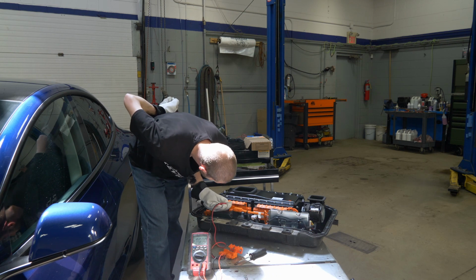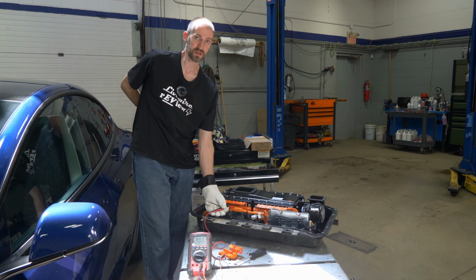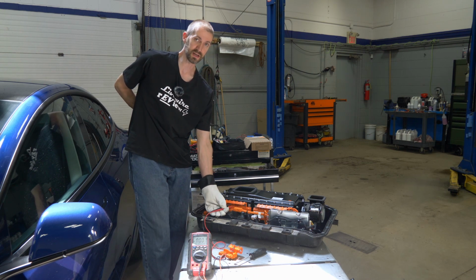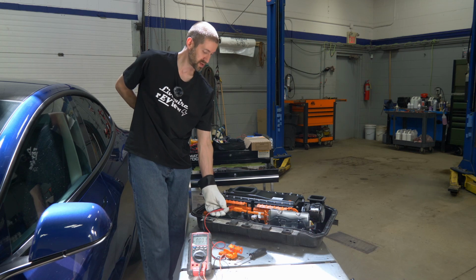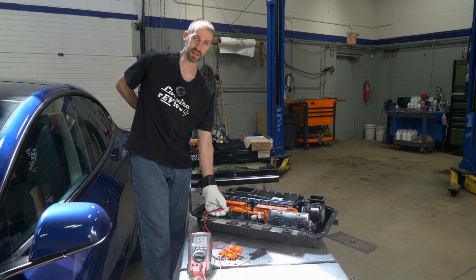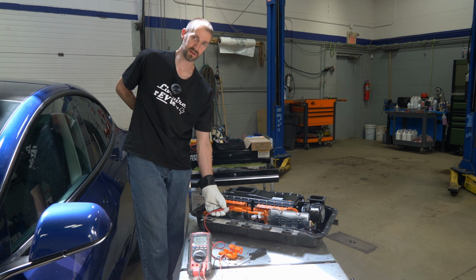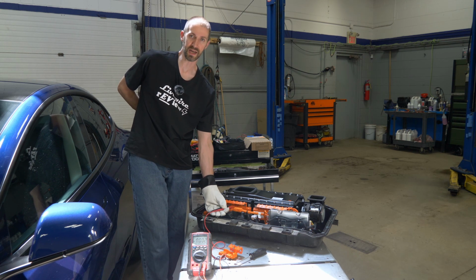29.45 volts. Now, the way a battery management system works is all these cells, modules, and everything have to stay within the same voltage range. And the reason you want them to stay so close is because if one cell or one module was slightly higher or slightly lower, it would actually get used more than the rest of the cells and it would wear out prematurely. And you can't have that across a battery pack. All the cells have to wear at the same rate. If they wear out at different rates, then your battery will fail prematurely.